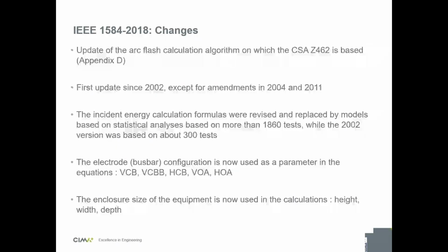So let's begin by stating the changes. For the Canadian listeners, the CSA Z462 is the safety standard in Canada, and it refers to the IEEE 1584 for its method of calculating arc flash. So basically, IEEE 1584 is an international standard for arc flash studies, and a bunch of local standards refer to it. So it's the first update since 2002. There's been some amendments back in 2004 and 2011, but it's been a long time since there was a new version. So it took about 16 years for the IEEE to come up with new equations to better represent the arc flash phenomenon.